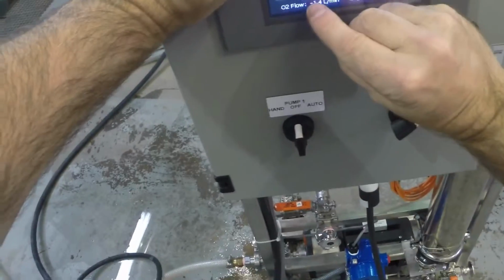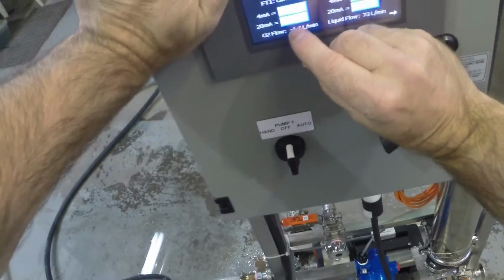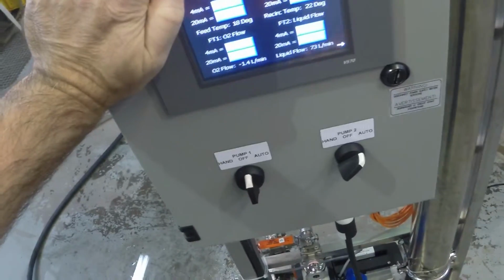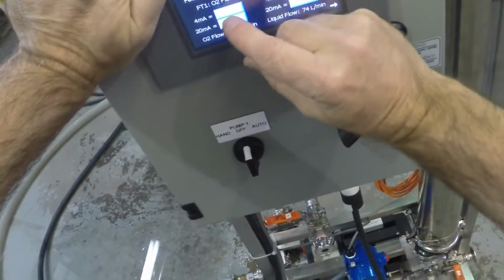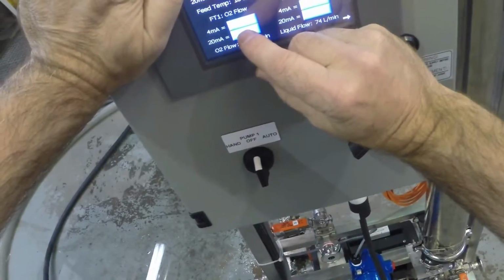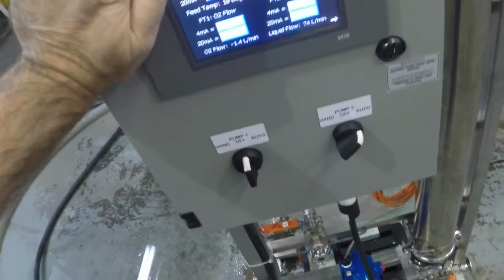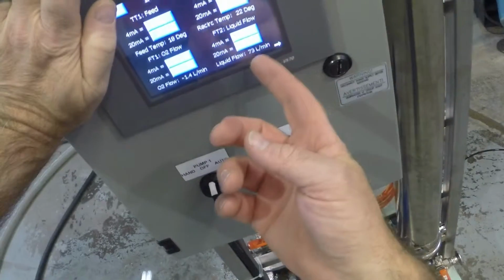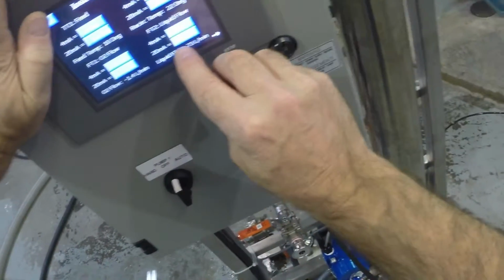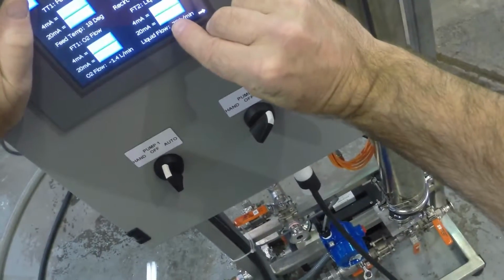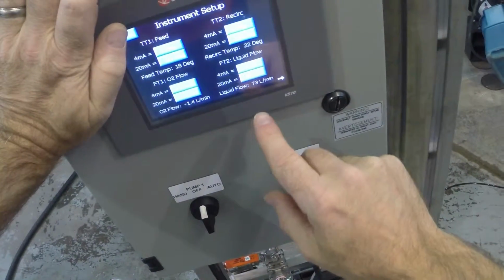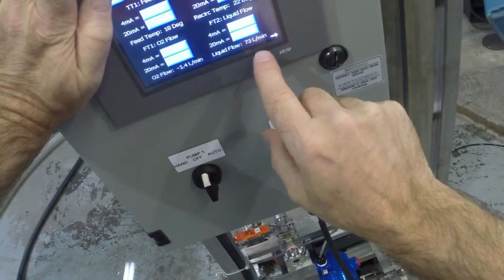Oxygen flow at 20 milliamps, it's referenced to 6 liters per minute for this meter that we have. At 4 milliamps, it means that it's at 0 liters per minute as the flow increases or decreases. Same with the liquid flow. 20 milliamps is calibrated to 108 liters per minute. That's full flow. Right now our liquid flow is at 73 liters per minute.